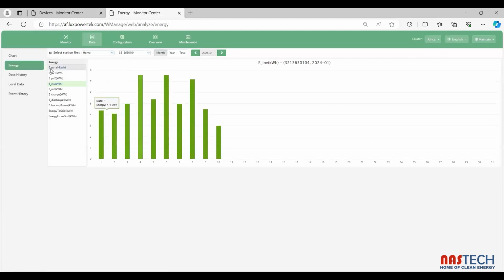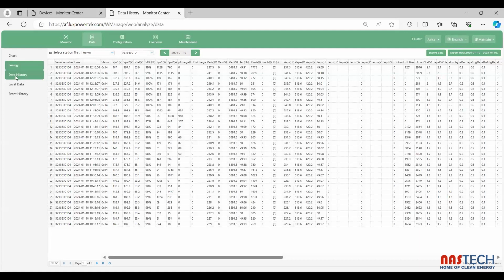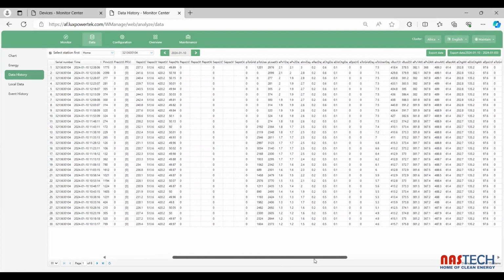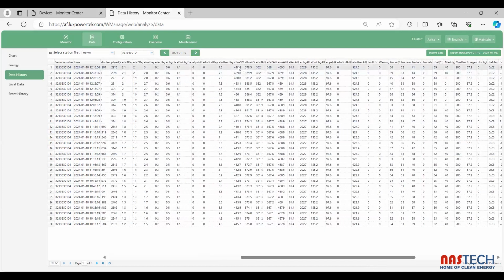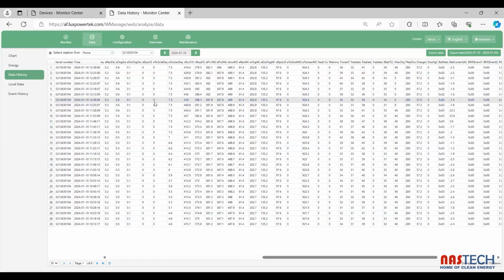Energy, that's your energy history, data history. Data history is one of those important tabs that you would go into to search for any irregularities that happened on the inverter. Here you would see the status code. The first is the sampling of the PV, the sampling of the battery, the conversion of that into SOC. Along here you will get the bus voltage as well. Here are your bus voltages. In some cases, the engineers in China also assist with interpreting the data on this data history. They help interpret the data and give you a better explanation of where the fault occurred and what the data was at that point.